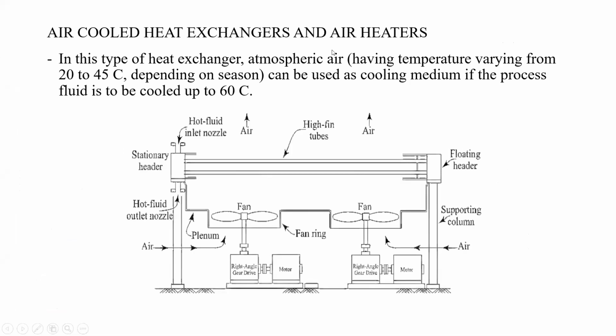Now, air-cooled heat exchangers and air heaters. In this type of heat exchanger, atmospheric air has different temperature, and that temperature depends upon the season. Like in winter we have less air temperature, and in summer we have more air temperature. So this air can be used as a cooling medium, if the process fluid is to be cooled up to 60 degrees centigrade. So this is the limitation of air-cooled heat exchangers.